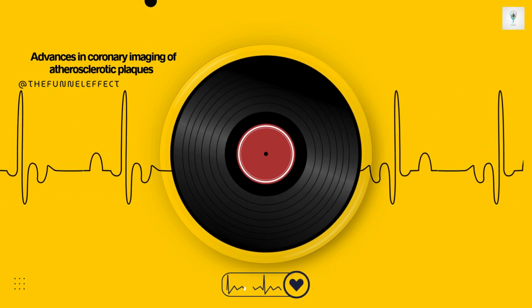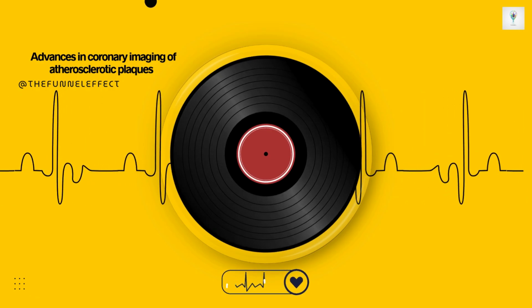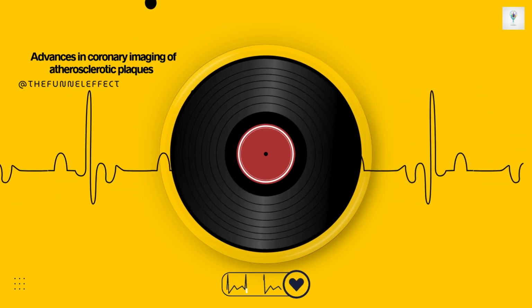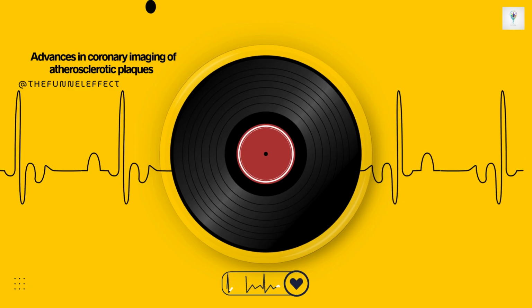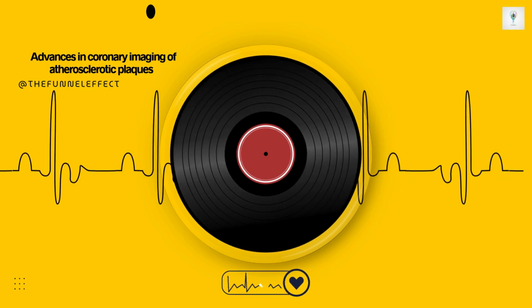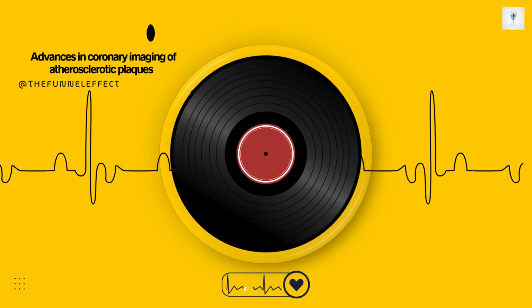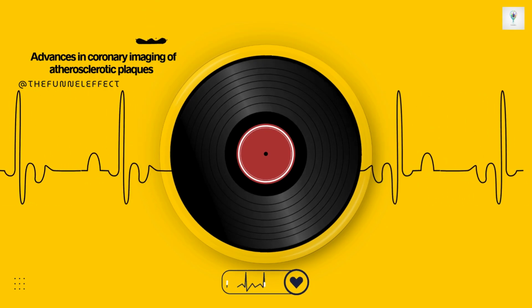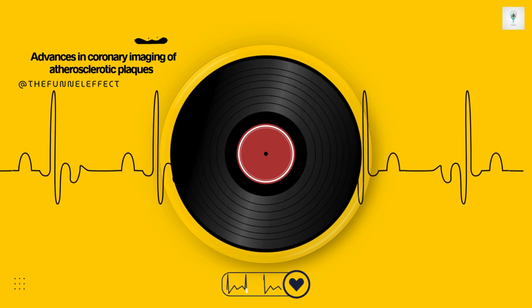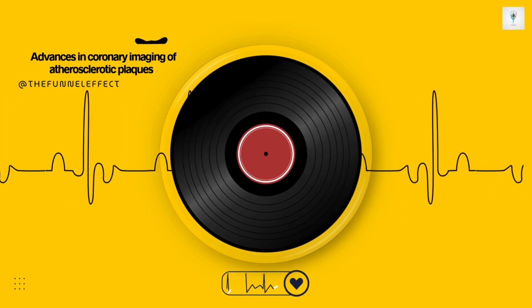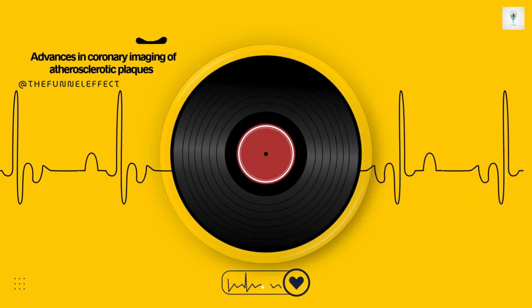The two big players here are IVUS and OCT. And the fundamental difference is the physics, right? Sound versus light. Exactly. And understanding that difference is key to understanding their strengths and weaknesses, their trade-offs. Intravascular ultrasound, IVUS, uses high-frequency sound waves. Its resolution is pretty decent, around 150 micrometers.